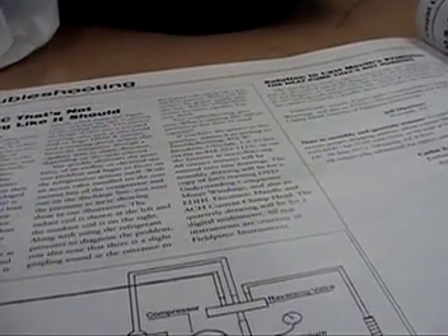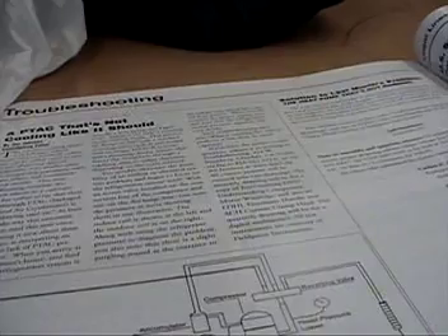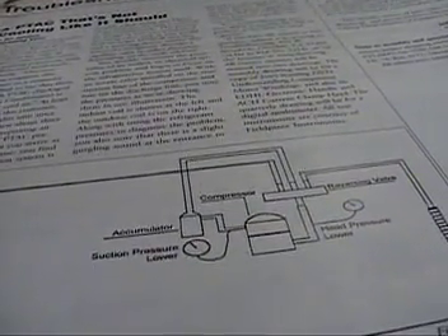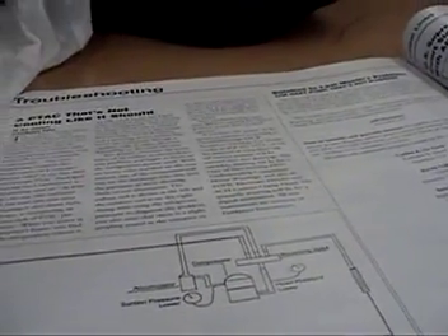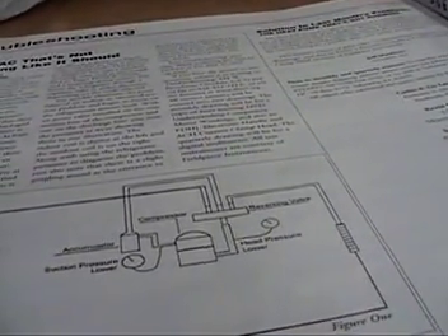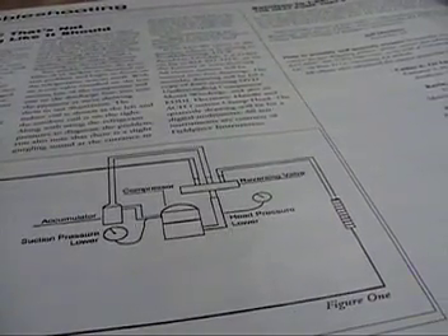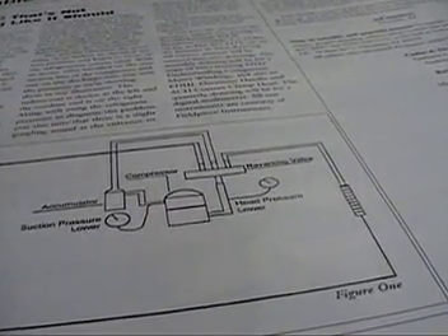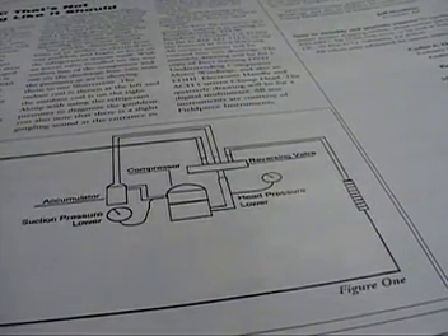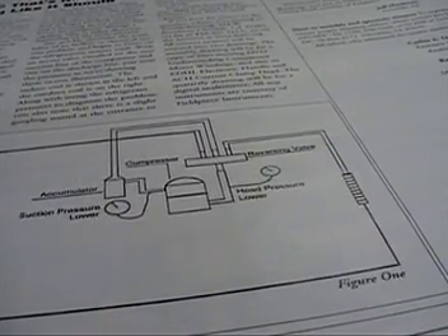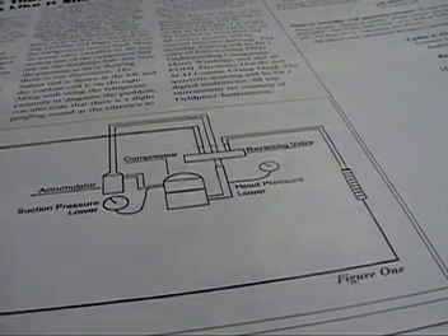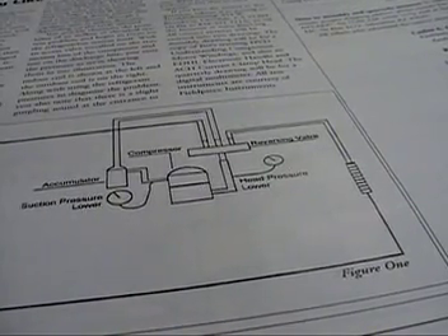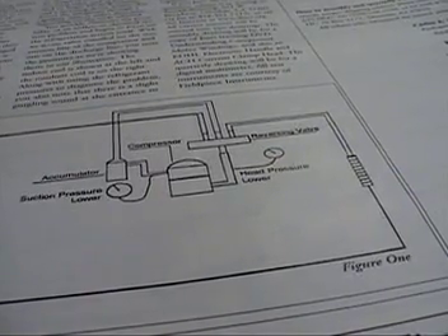Could it be a restriction? Did they tell you anything about what the pressures were? God, it could be anything. Sounds like a restriction. Well, they put a pressure gauge on. They put a line tap, but they didn't tell you what the pressure was. Didn't give us any numbers. Oh, did I miss something? Did I miss that? And you note the pressures as we're showing them in our illustration. Okay, suction pressure lower, I missed that, yeah.